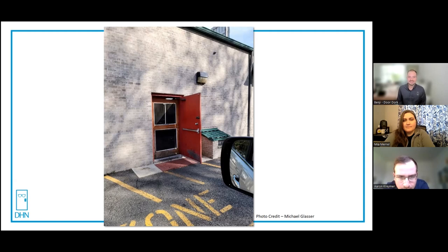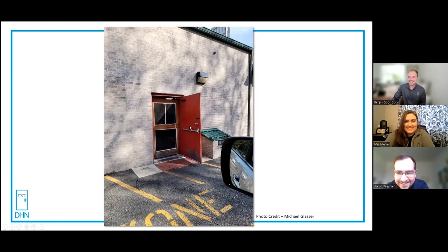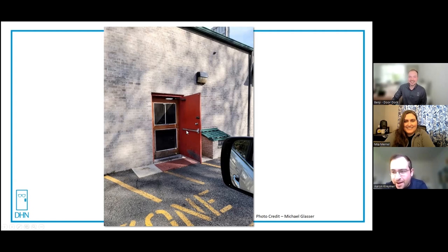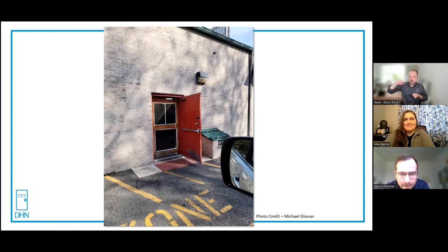So, I would say when it comes to different codes, life safety trumps all of them. So, if there is a life safety issue like on a path of egress or an exit like this, it doesn't matter if it's hurricane rated. You still have to be able to egress in the case of that kind of emergency. What is that? So, you have the push bar and then you have, I'm guessing, a bolt on the top. What's in the middle? That's a knob. I don't even see a latch for that. There isn't a latch for that. You caught that.